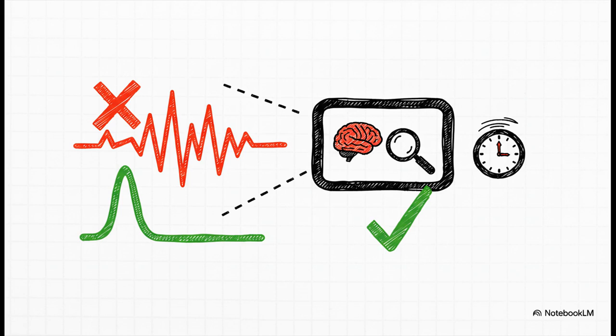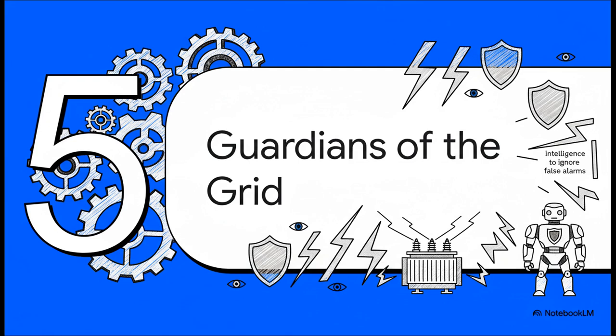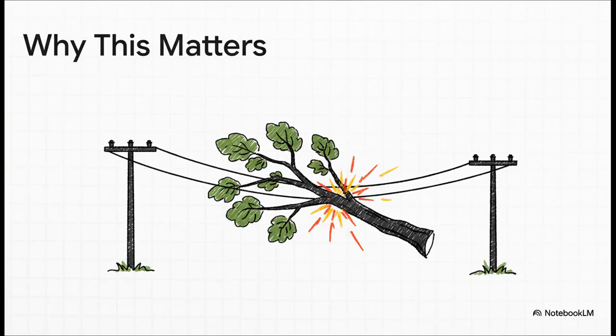This is where the smarts come in. Modern relays are way more intelligent. They're designed to recognize the unique electrical signature, the specific shape of an inrush current, and they're programmed to just wait, just for a fraction of a second, to see what happens. If the huge current spike disappears right away, the relay knows, okay, just waking up. If it stays, then it knows it's a real fault, and then it trips the breaker. So when you put all these pieces together, the instant fault detection, the perfect balance check, and the intelligence to tell a real threat from a false alarm, you get this truly remarkable protective system. These aren't just pieces of equipment. They really are guardians.